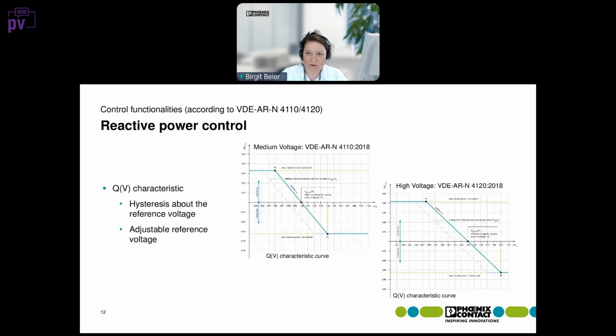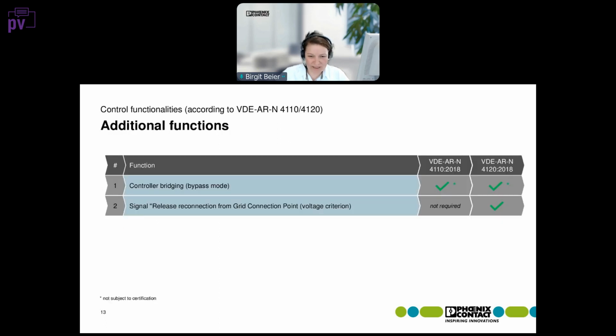There is another small example for this, or how it looks in the VDE. You have 2 characteristic curves, one for medium voltage and one for high voltage. The difference is that the intersection is shifted slightly from 1 to 1.004. It's the same again: if the voltage is too high, then the power has to be reduced. What else do you have? You have a hysteresis about the reference voltage and an adjustable reference voltage. What more do we have? We have some additional functions. Of course, something standard, a controller bridging, and a signal release for reconnection from the connection point with voltage criteria. Let's have a quick look at this as well.